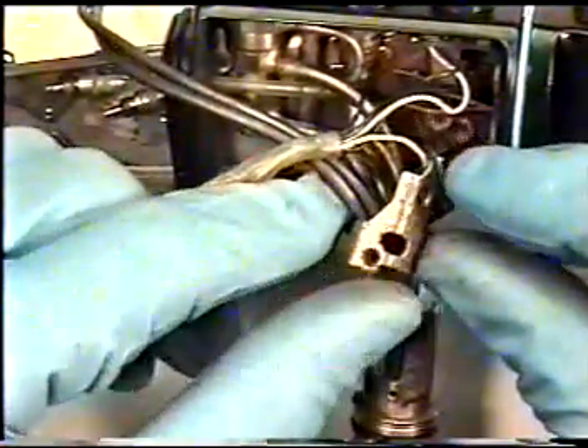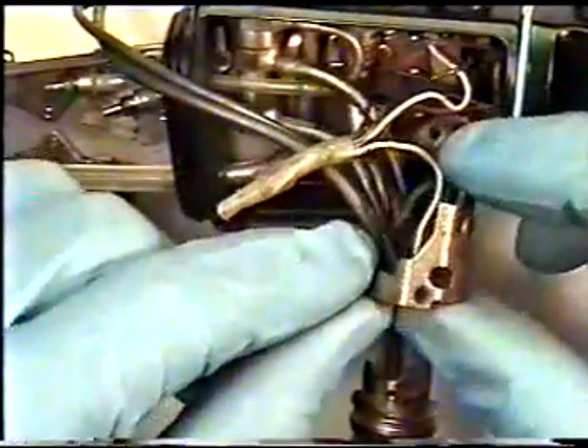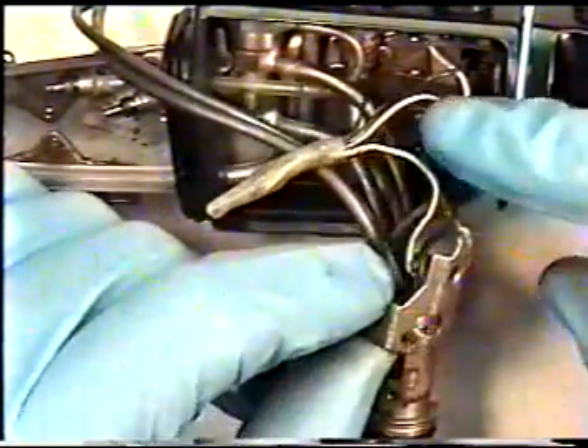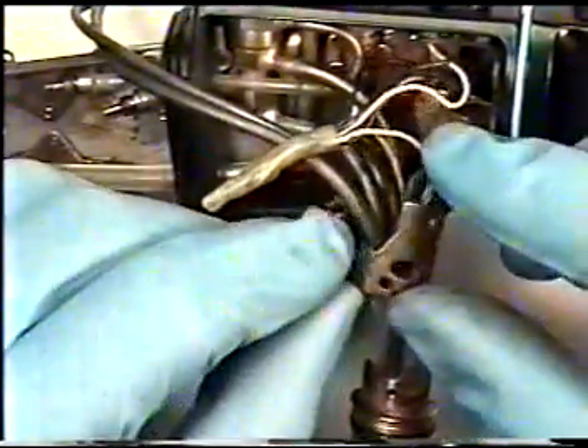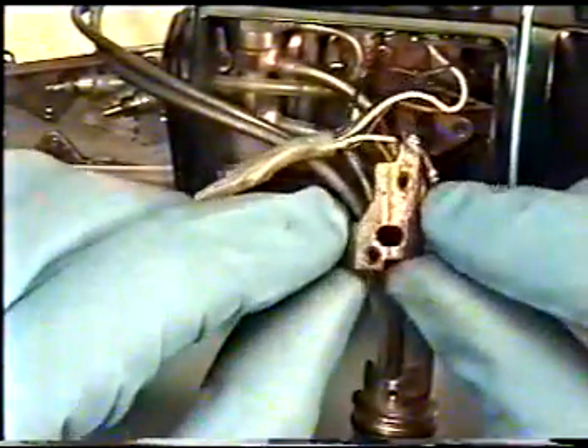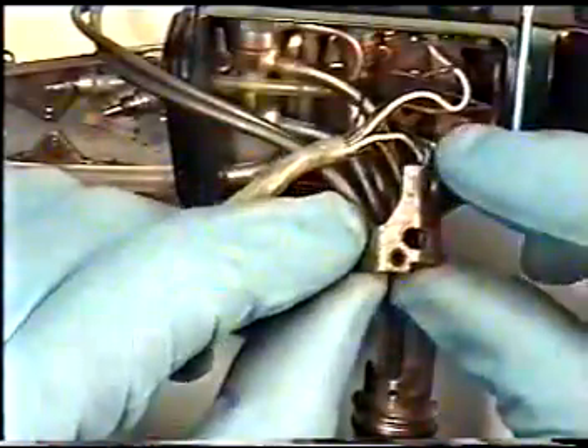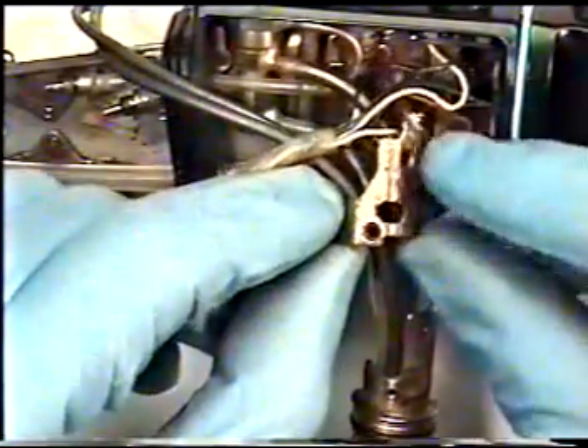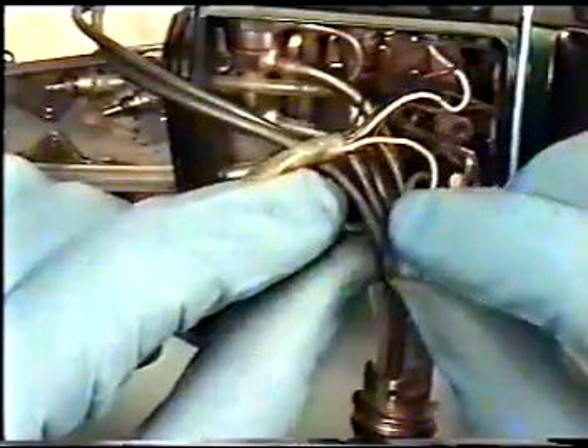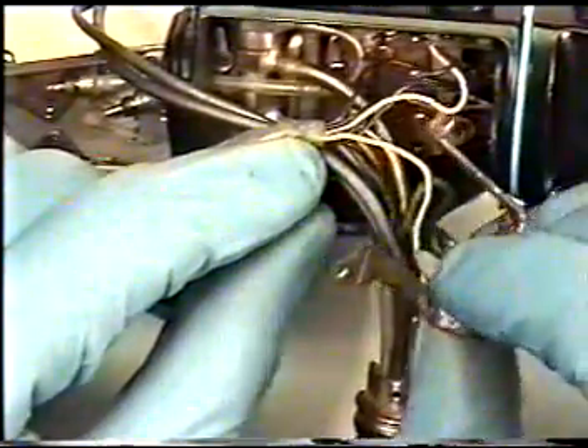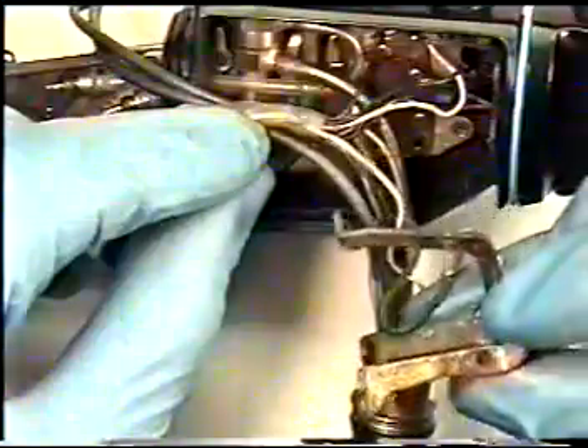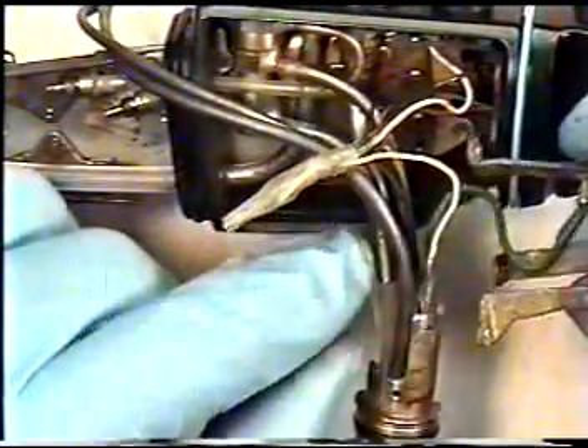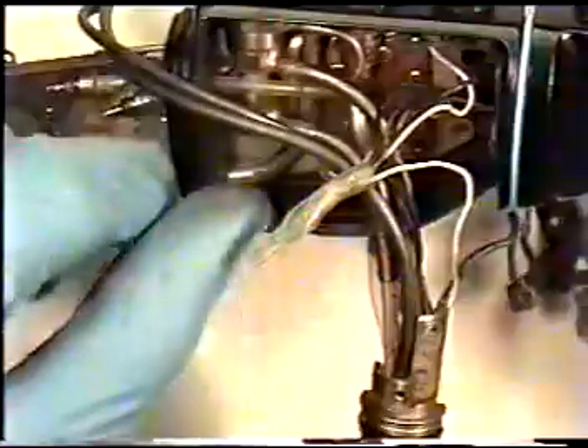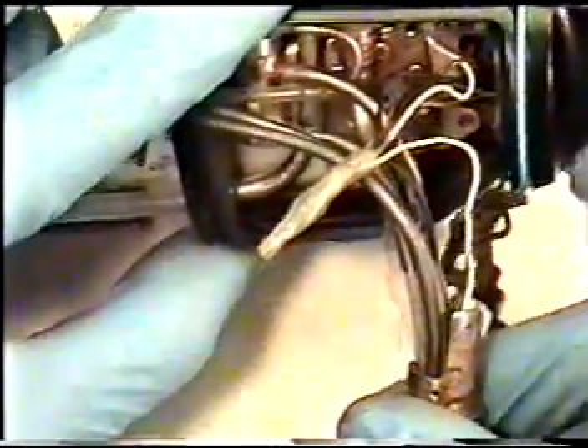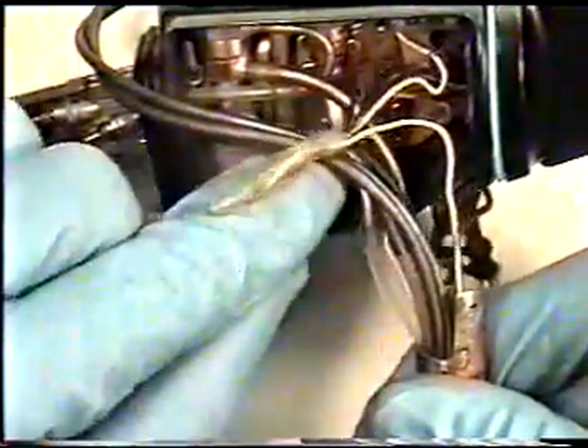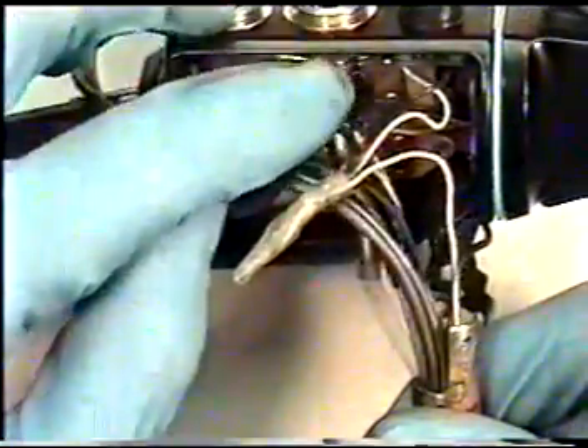Now, being extremely careful, remove the 3-leg bracket from your body control section. If this is a fiber scope, it will be very critical that you do not trap, pinch, or crush your image bundle, which would run directly underneath this bracket. Carefully slide bracket out and away from your bundled wires and suction channel. We now have access to the suction channel, which we will need to cut off and remove from your suction channel assembly.